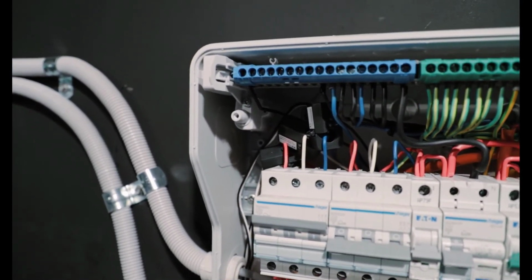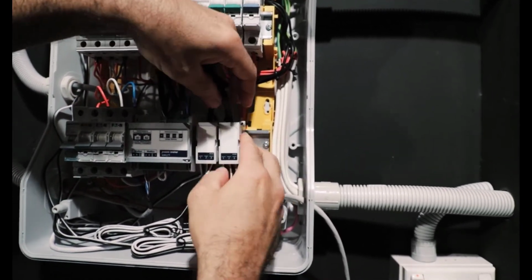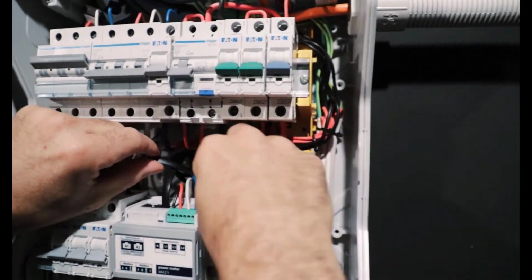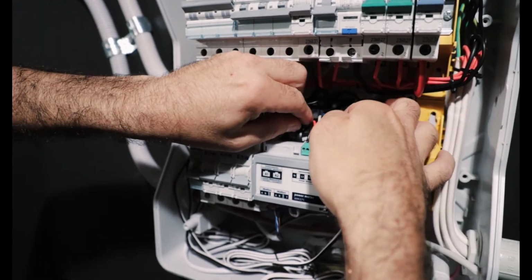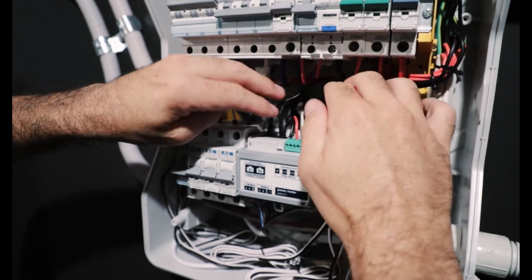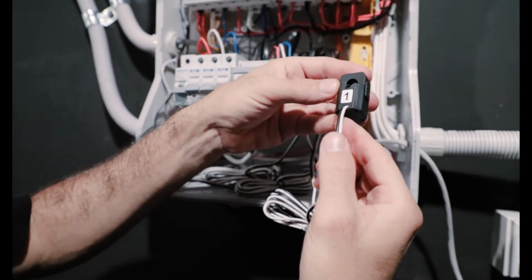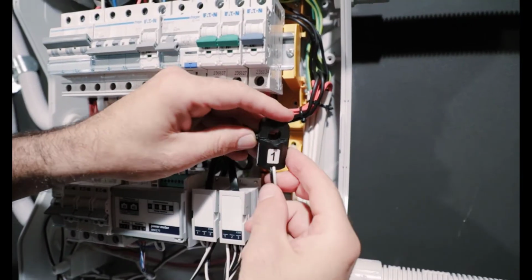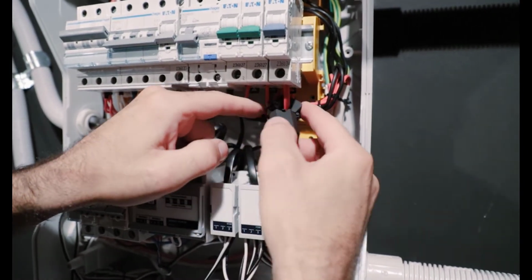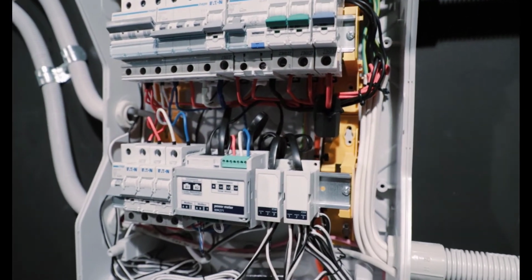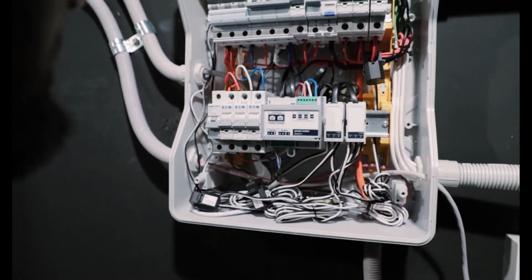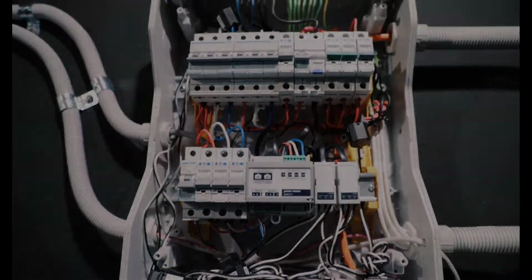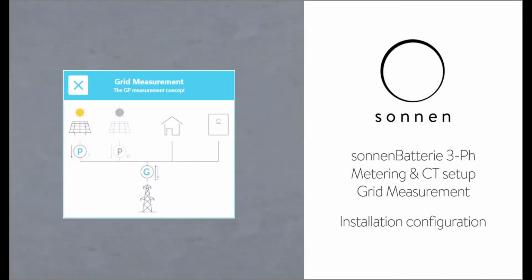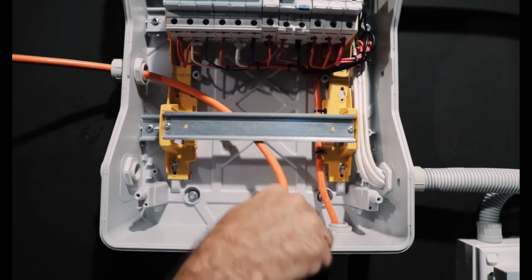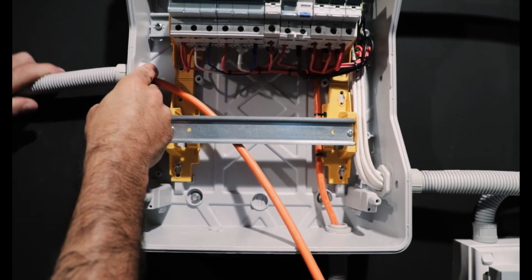So there we have CTs 1, 2 and 3, and we now put on our transducer set for the solar connection. For this installation, it's actually just got a single phase PV installed, so all we're going to do is take CT number 1 and connect that through. As this is a consumption measurement, the Sonnen system knows it's a consumption, so it will take out the PV from the overall total. Now we're going to do a 3-phase configuration in a grid measurement. So this is going to be looking at power flow in and out of the grid. It's going to have the solar taken into consideration by the Sonnen system.